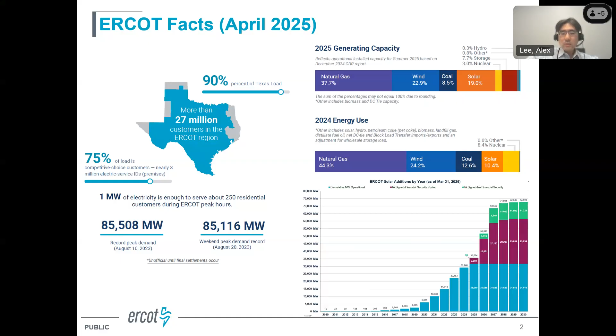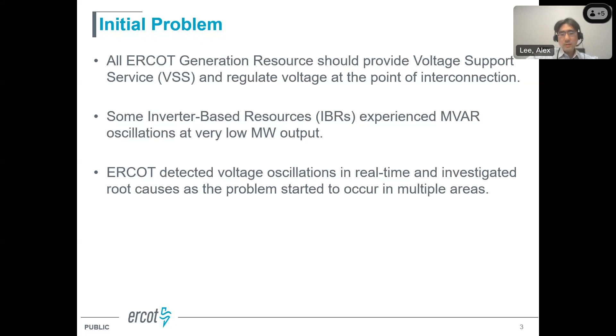There's been a lot of challenges with solar, especially at nighttime when there's not much megawatt output and solar plants are unable to provide proper reactive support. The initial problem was that ERCOT rules require all generation resources to provide voltage support service and regulate voltage at the point of interconnection. However, some inverter-based resources, including especially solar power plants, experience megavar oscillations at very low megawatt outputs, which triggered ERCOT to start a root cause analysis investigation, since we were seeing these issues popping up in multiple areas across the ERCOT footprint.